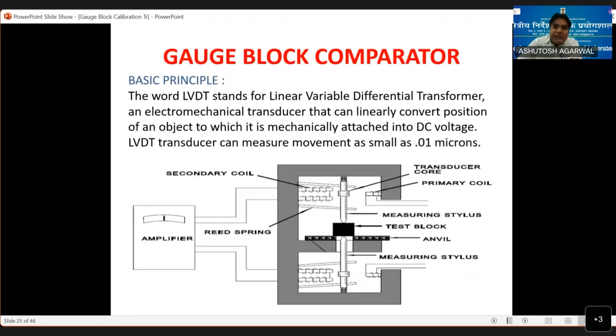Okay. So the basic principle is, this works on an LVDT, a linearly variable differential transformer, an electromechanical transducer that can linearly convert the position of an object to which it is mechanically attached into a voltage. And we read the voltage, but that voltage is just read. That will not give the exact dimension. You take the change in voltage in each gauge, and that voltage change you convert. There's a method. Okay.